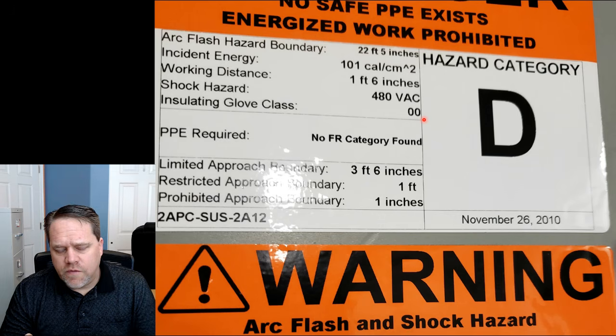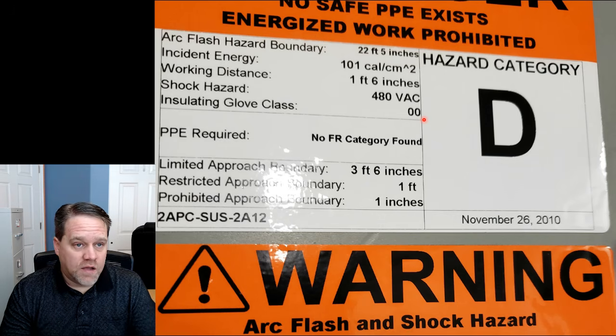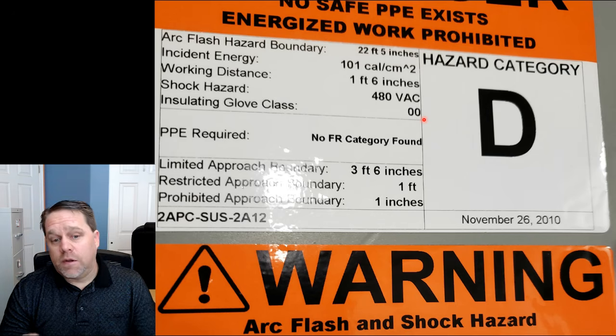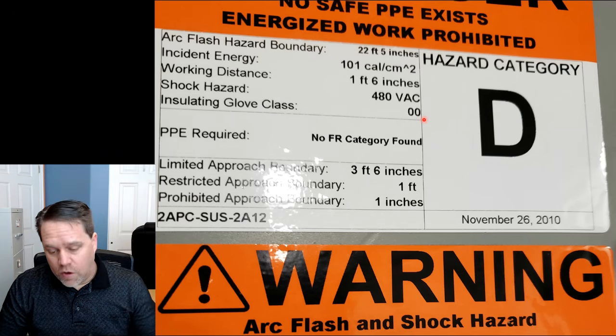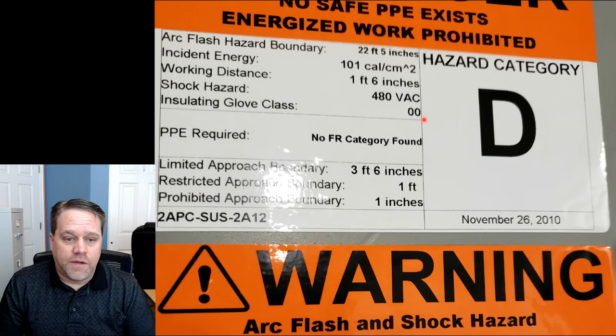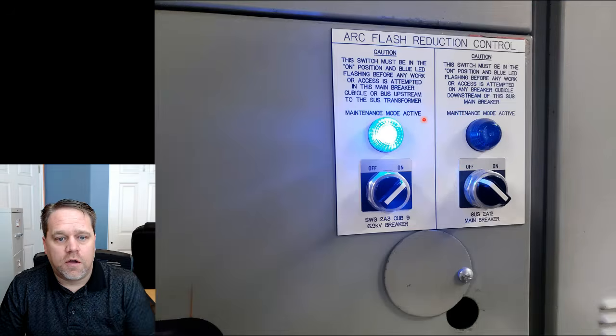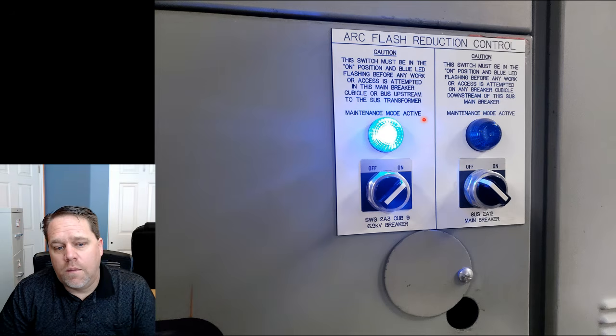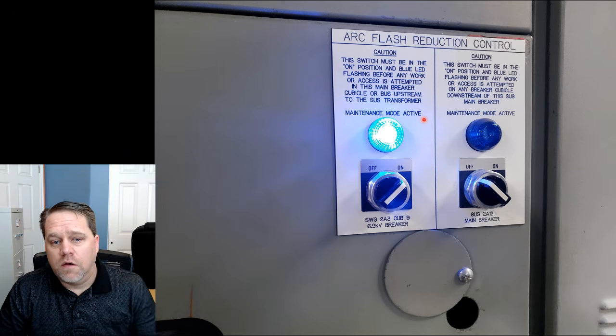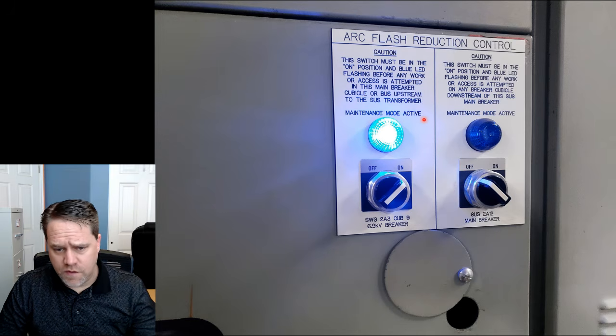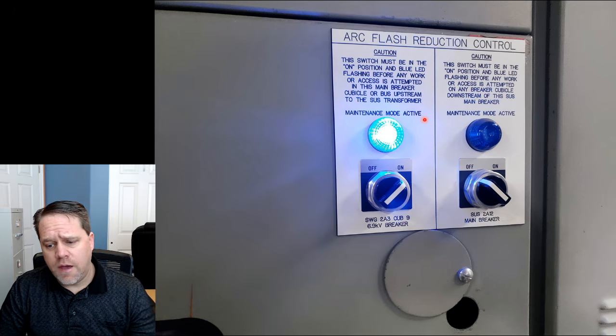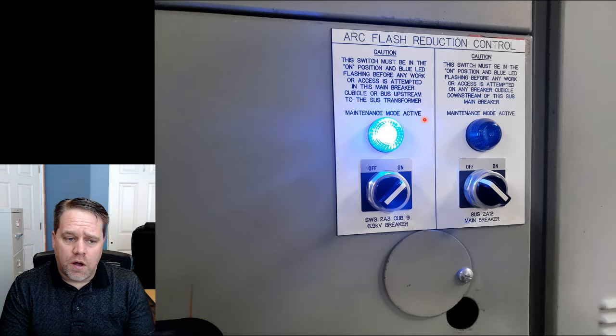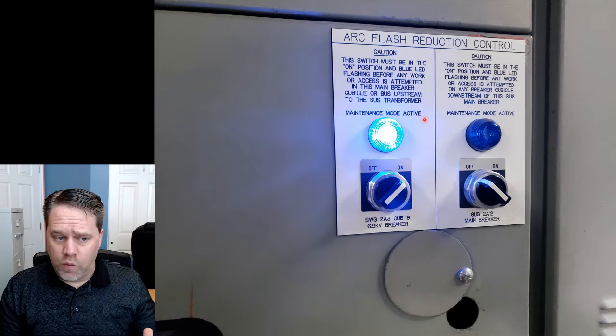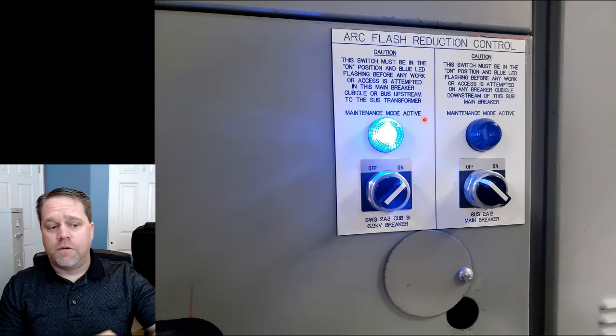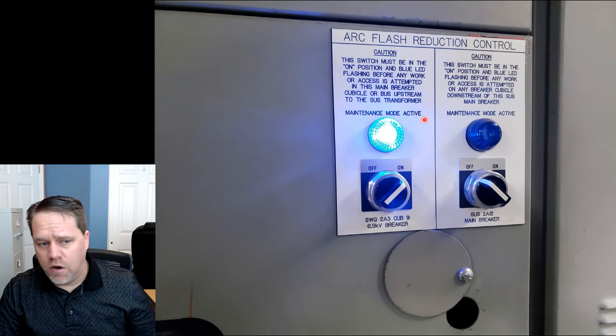So here's a piece of equipment that I have to work on energized, and if it blows up, I'm dead. So how are you supposed to work on that safely? Well, what you do is you go back over to the equipment and you put the equipment into maintenance mode. And what they have is a system, a maintenance switch, and when you turn it on to maintenance mode, if anything goes wrong, then the device will open very, very quickly, long before the incident energy even gets to 101 calories.